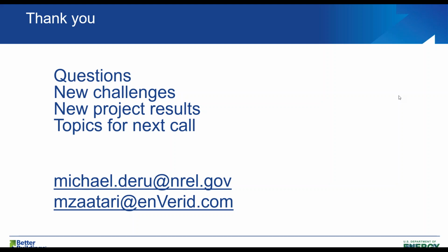What was the second question? The second was, were savings based on after all the optimization strategies were implemented for chillers. Yeah, so you can look at this easily: what the HLR does is it reduces the amount of outside air. In summary, you are reducing the load on your cooling system or heating system. So if you have a better chiller, you can calculate the energy savings by putting in a better efficiency. But still, it cuts the load. Now, if you have a very efficient chiller with a high COP or low kilowatt per ton, then your savings will be lower. We can do this calculation on a specific project, for a specific climate, or for a specific outside air reduction.